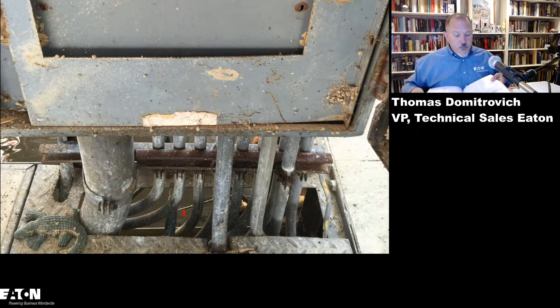This panel board is on that docking station, or on the pier, and then they may put multiple panel boards, which drove a change in the 2020 cycle to recognize multiple outside feeders in Article 225. We made a change in 225 to permit multiple feeders to a structure, and we modified the definition of a structure too.